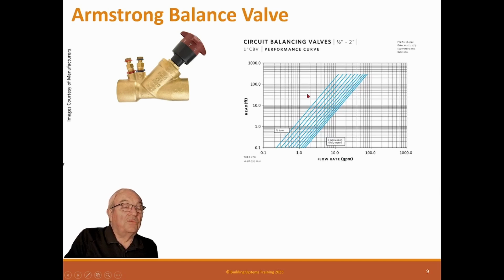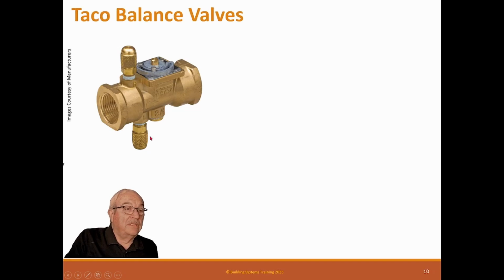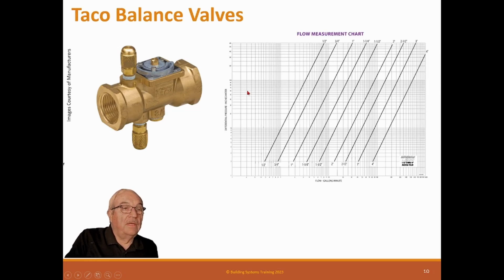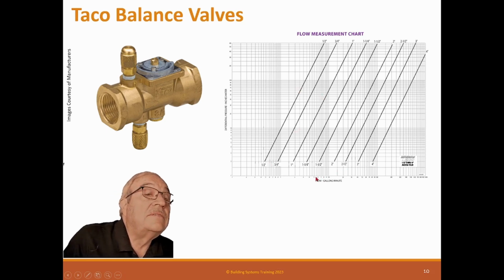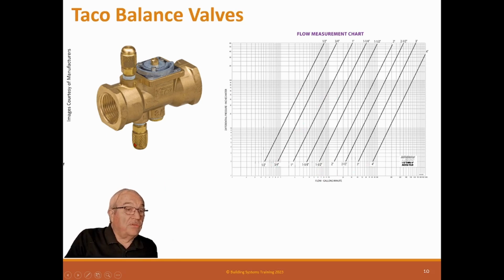Here's another one for a range of different kinds. So this is a bigger valve. And they make this balance chart for each size of valve. So you just, in the submittal, it should have been in the submittal for you, and you can balance this valve and read this valve directly from there. Taco makes one. So you're reading pressure across the orifice, and you're adjusting here, and you can lock this one down. And again, it's just like the other one. It has the valve sizes, and here's your pressure reading. So basically, when you go to the field, you hook it up to your instrument, read the flow, adjust the flow, and read it to where you get it, and then you're done.